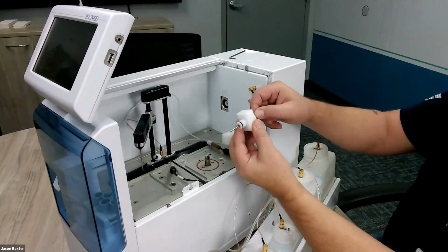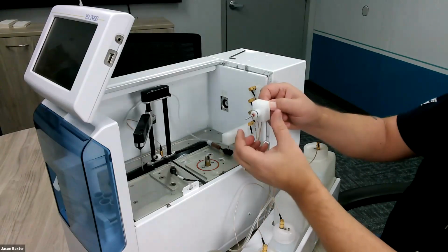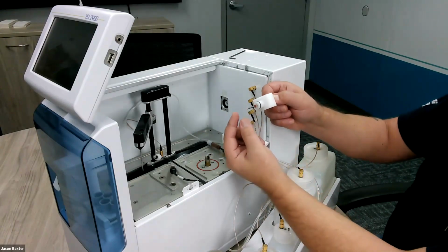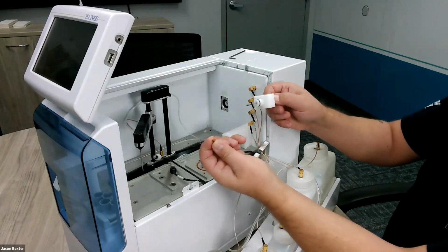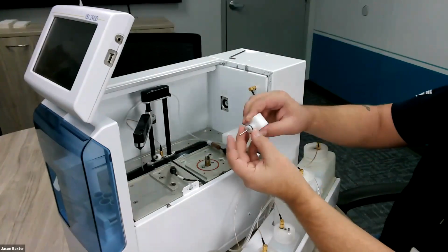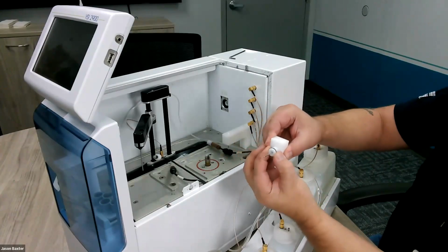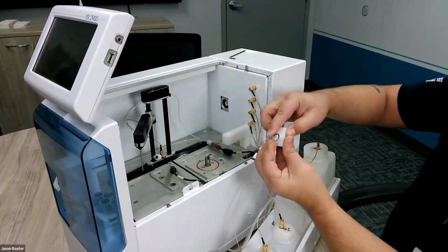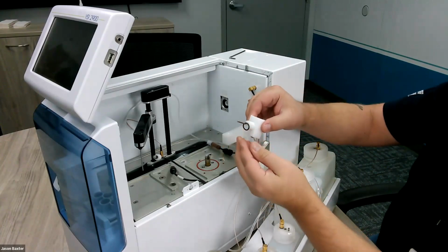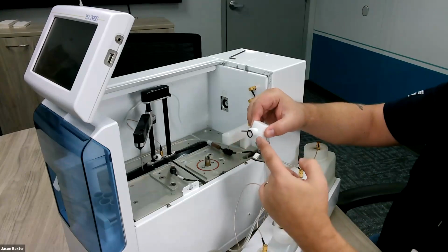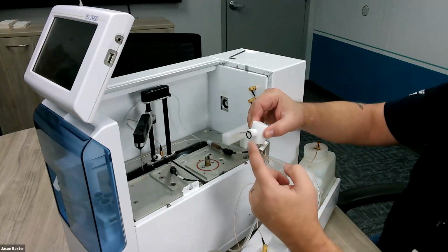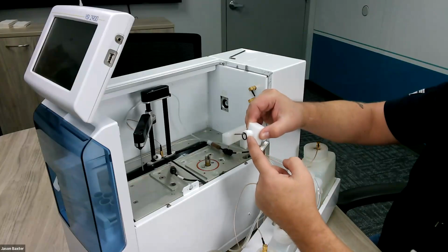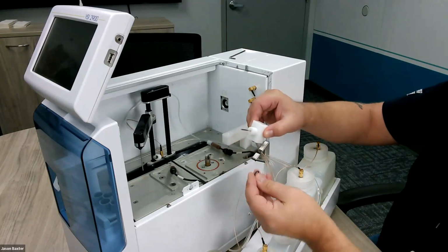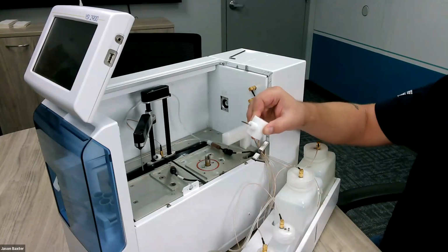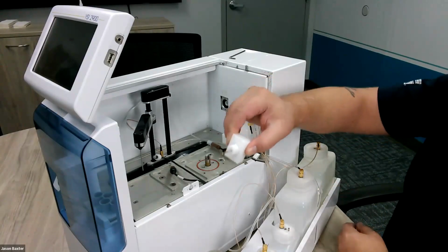Lastly, you can hold this chromed part of what I call the T-bar, and you can usually unscrew the sipper pump body in, and now it's exposed to the second O-ring. Remove the second O-ring. Last, take off this black O-ring by pinching and pushing upward, and then you can walk it off. I want to advise, you want to try to do this by hand. If you use something metal like a pair of tweezers or a screwdriver, you can end up gouging this white plastic body, and then you're going to introduce a leak where you didn't have a leak in the past. So you want to be very sensitive with that part. The black O-ring you can discard. Set this to the side, ideally with your 2 bolts that hold that assembly together.